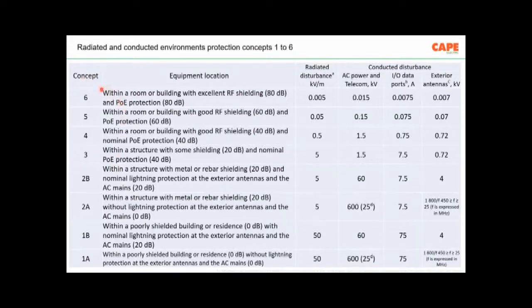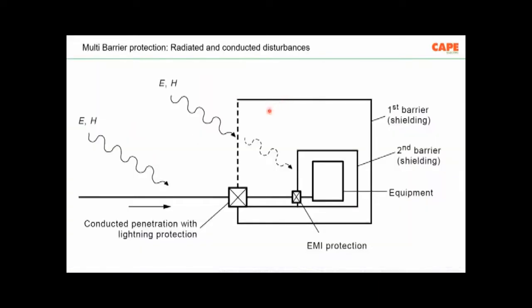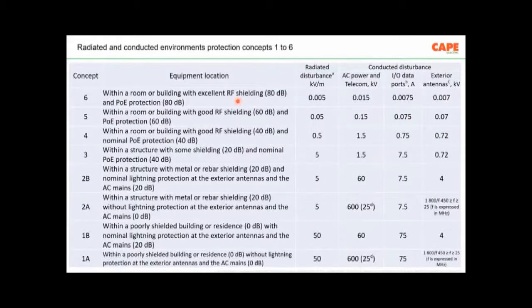Protection of a facility means the first shielding, for example here, the first shielding or barrier shall protect your building. Your building must give a certain amount of electromagnetic shielding against conducted and radiated surges, for example. Now, if we have a good quality electrical building which is supporting modern electronic equipment, preferably concept 3 or 4. This chart is actually from IEC 61000.